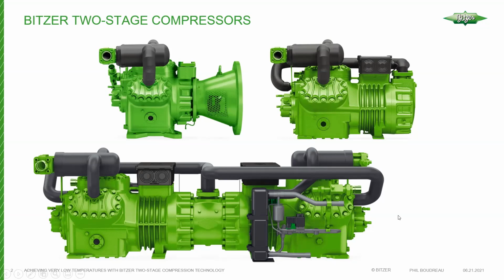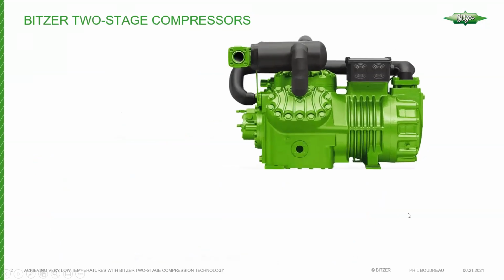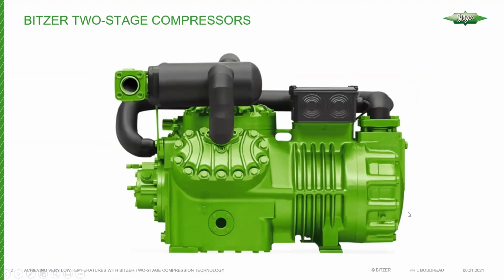So these are quite a bit less common in North America, but these are another product that BITZER produces, and they all achieve the same goal. This is refrigeration generally that you can operate down to about minus 90 Fahrenheit saturated suction temperature. So here's the compressor that we're going to focus on here.